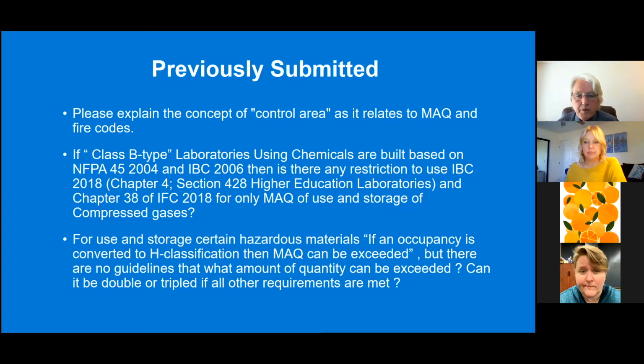If you're doing a construction job, you can improve the quality of the segregation and fire resistance of the area you've converted, but you really need to look at that. And in some cases, you're right, there are no limits other than the physical limit of the material you can put in the space. In the 2001 code, they had a limit of a control area of 10,000 square feet. That may still apply to some of the hazard classifications, but it depends on where you are, what aspects of which NFPA they might be applying. That's a challenge.